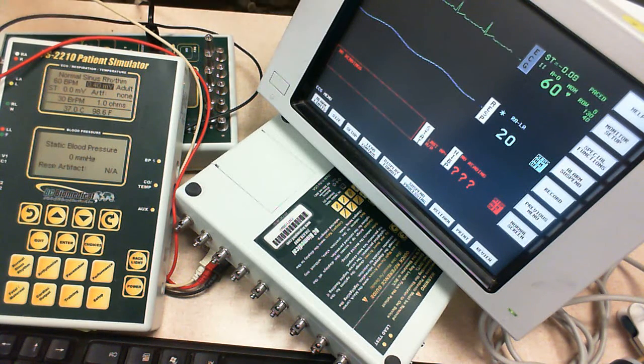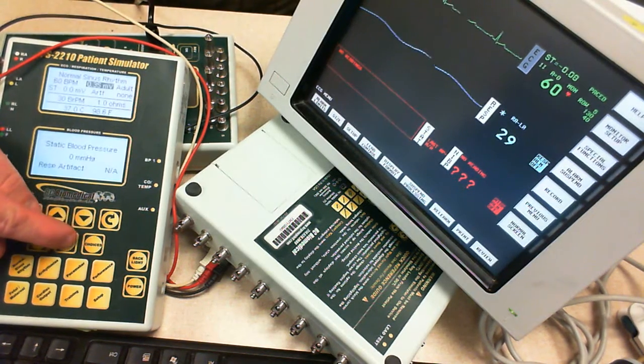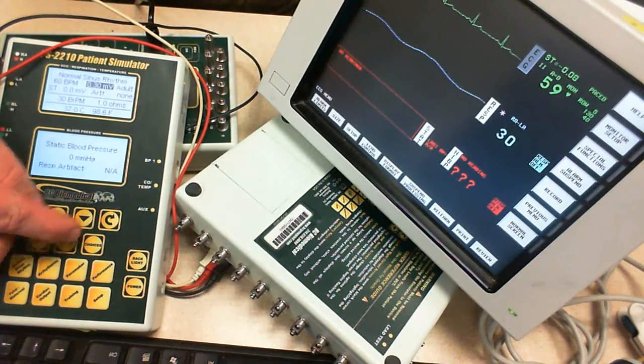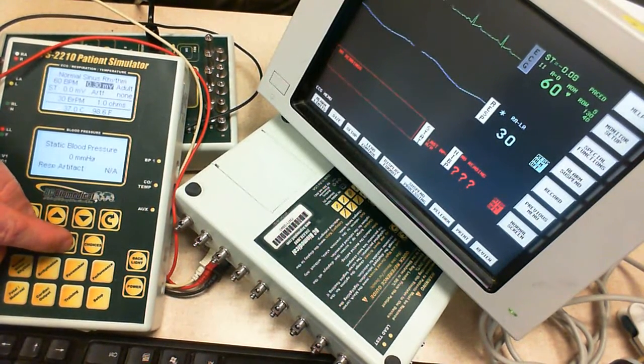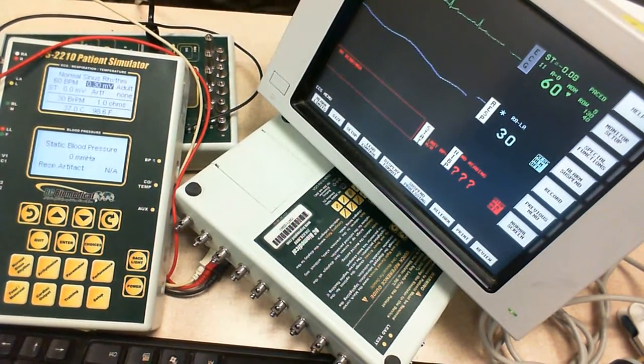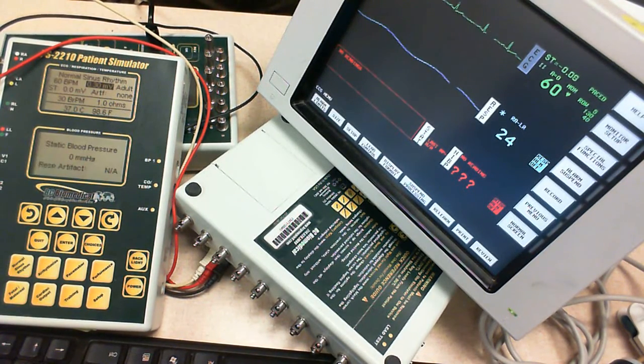So sensitivity asks a question. What is the minimum voltage that this machine will actually count the heart rate accurately on? Now, 59, 60, that's a little swing. That's not so bad. I'm going to go down here to 35. Let's go down to 30. You see how it's flashing 30. We're going to hit 30. And notice my wave keeps getting smaller, but my heart rate is pretty solid, actually.